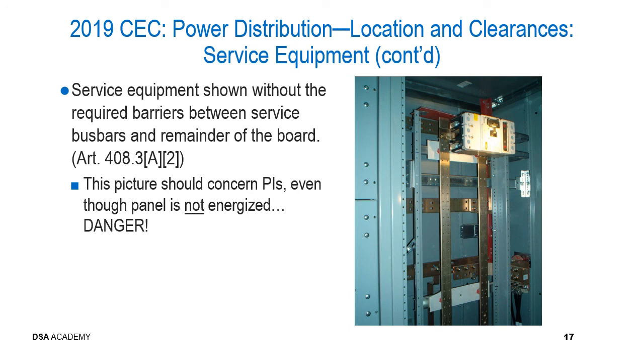This is a very dangerous situation, and again, we're not presuming that this particular panel is energized, but the thing to take from this is respect the fact that these are very dangerous areas. You, as well as all of the contractors and people in these areas, need to always respect the fact that these can be potentially dangerous, and you should always view any of these panels, switchboards, equipment, conductors, anything that is utilizing electricity as potentially dangerous. And also, of course, we've identified here that in Article 408.3(A)(2), service equipment is required to have barriers between the service bus bars and the remainder of the board.